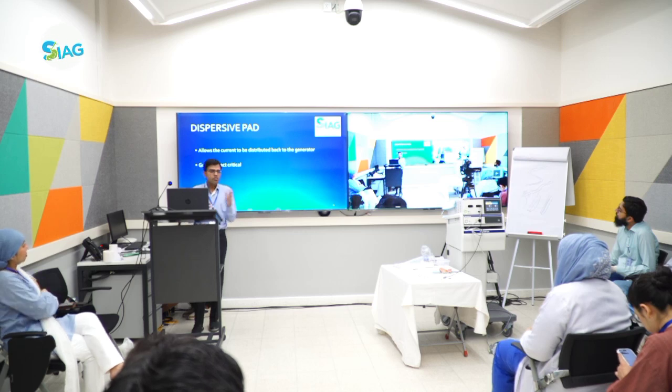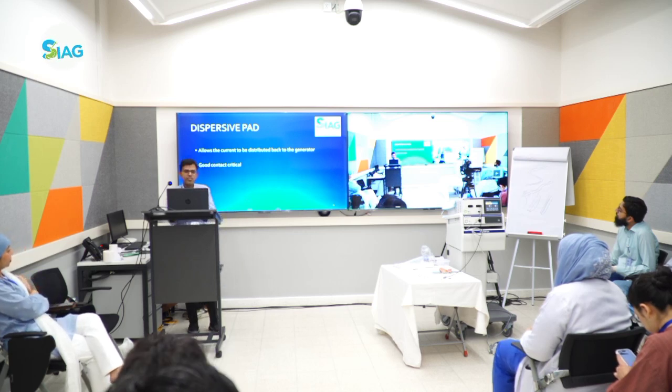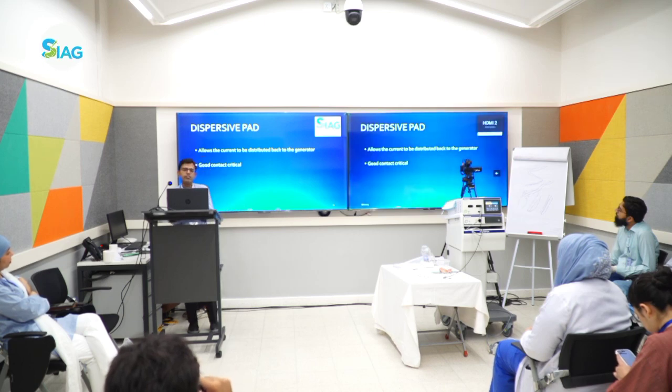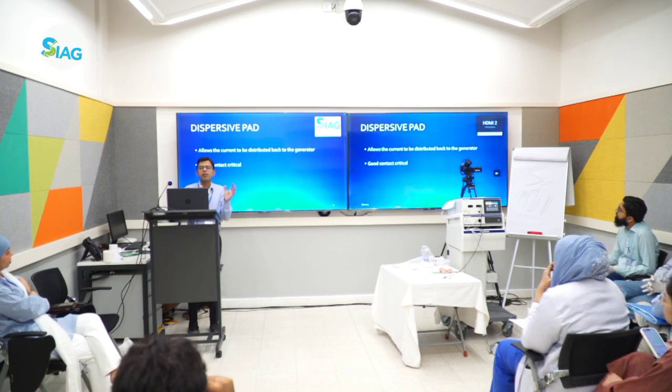So what is the use of dispersive pad? Obviously, it dissipates the excess heat generated in the body. It allows the current to be distributed back to the generator and completes the circuit.